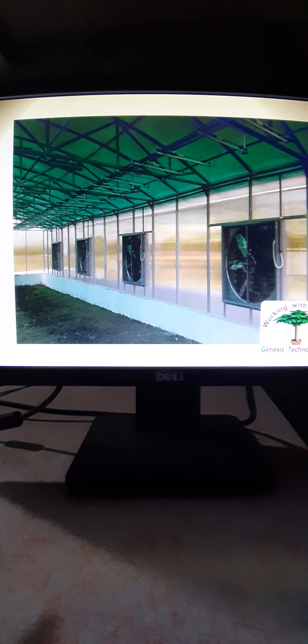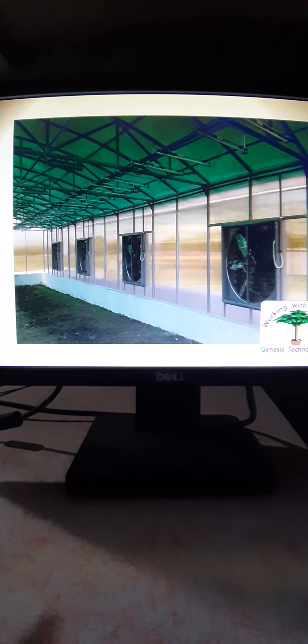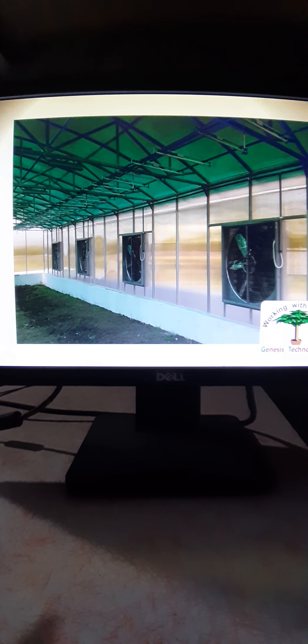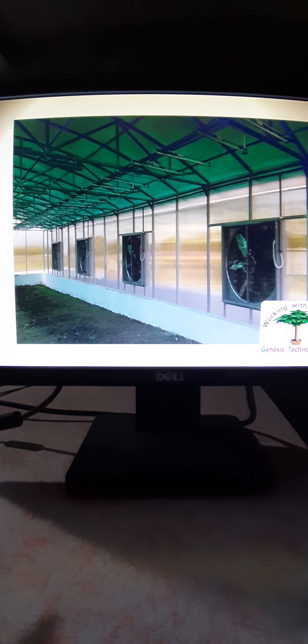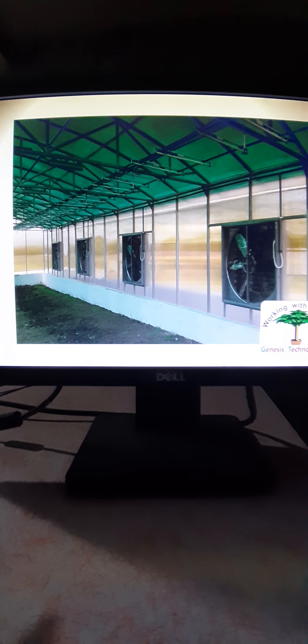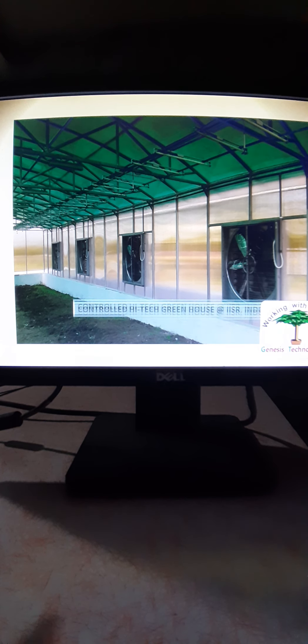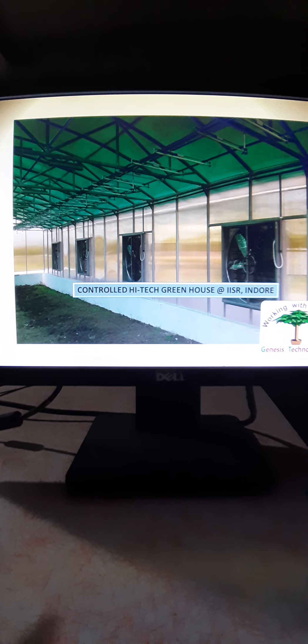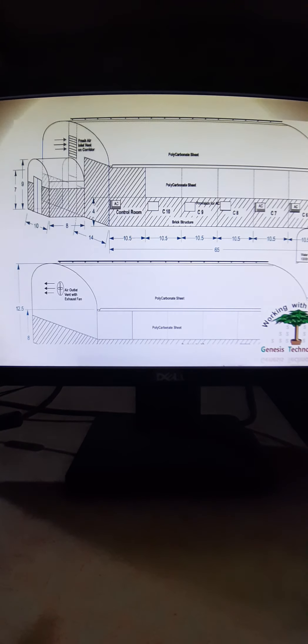This is the fan for controlling the temperature. It is used as an exhaust fan because on the other side you have the cellulose pad. Whatever temperature you want to set, based on that the opening of the fan is set in such a way that it can maintain the particular required temperature.